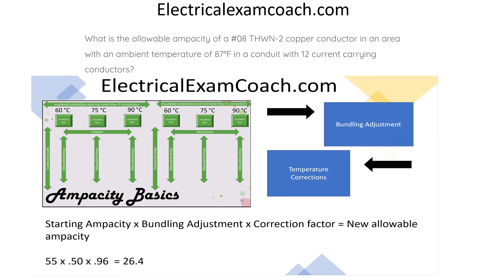Let's break it down. First, we start at our primary ampacity table on the copper side and check if our insulation type, THWN-2, is listed in the 90-degree C column — it is. So we choose our starting ampacity, which is 55 amps. Next, we head to our bundling adjustment table and find the adjustment factor for 12 current-carrying conductors. Then we head over to our temperature-correction factor table and find the correction factor for an ambient temperature of 87 degrees Fahrenheit. We start with our original ampacity of 55, multiply it by 0.50 for the bundling adjustment, and multiply it by 0.96 for the correction factor, giving us a new allowable ampacity of 26.4 amps.